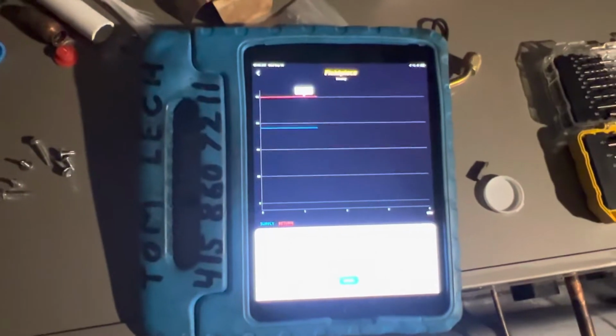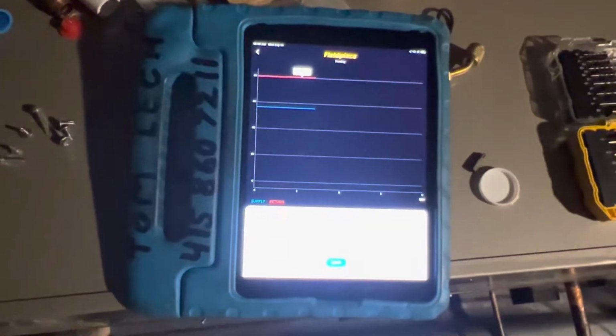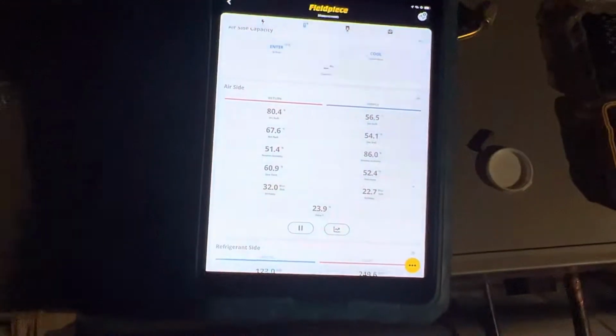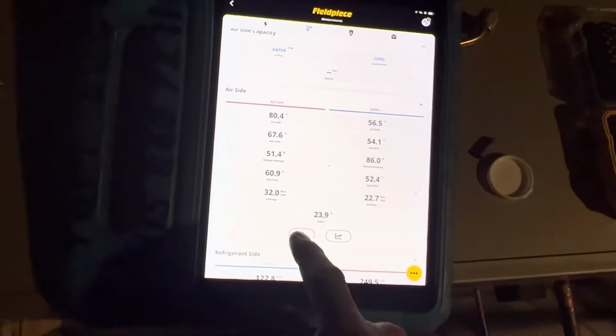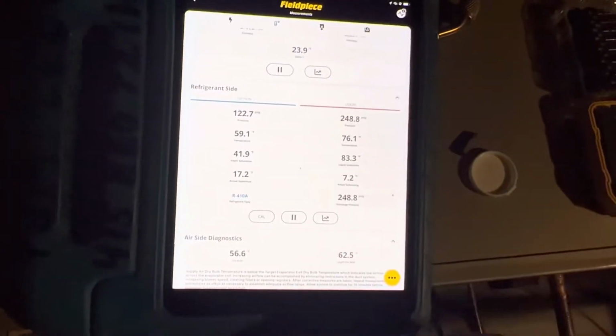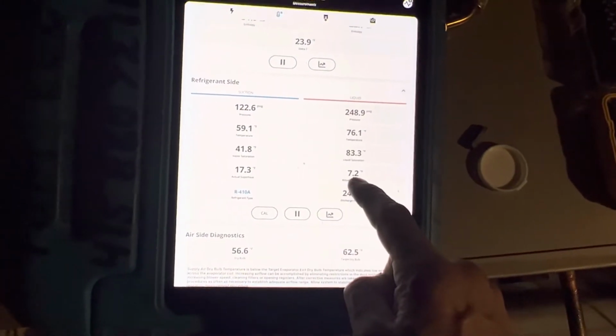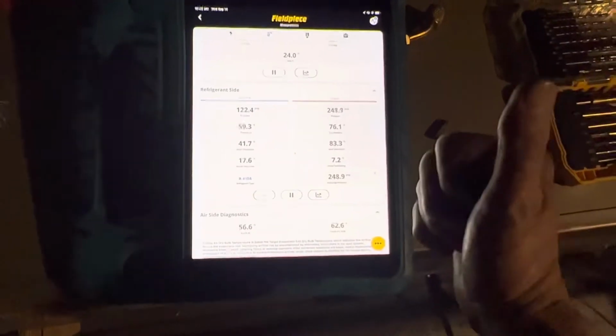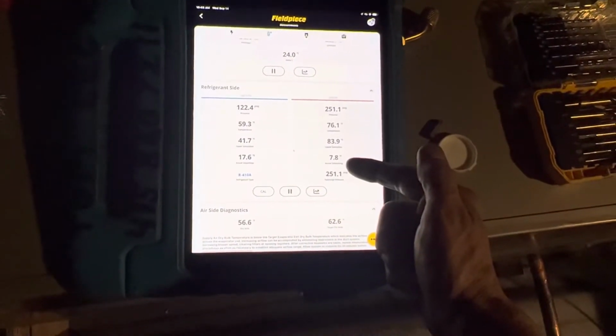I had them turn up the lights because I need a heat load in there, and I just turned off the other AC so I could get this close to charged in on the dial into charging. So if we go back over here, the outside label I think says it's supposed to be 14 degrees subcooling, and our subcooling is at 7.2, a little bit low on refrigerant. So I'll pump the refrigerant and get this close to their 14 degrees.